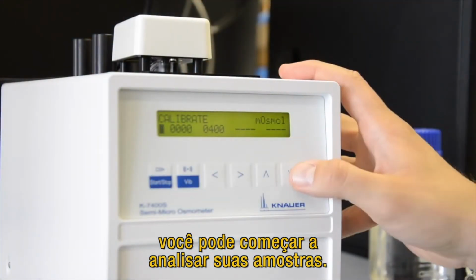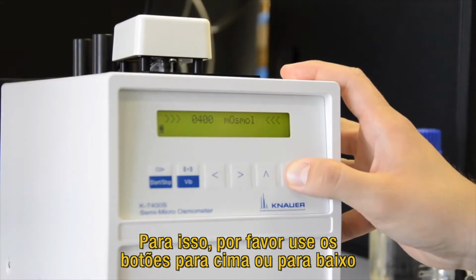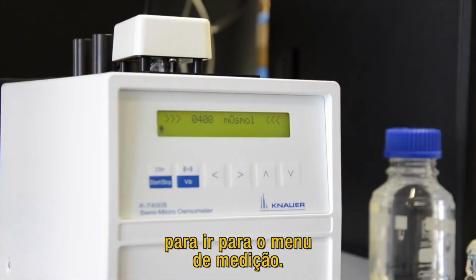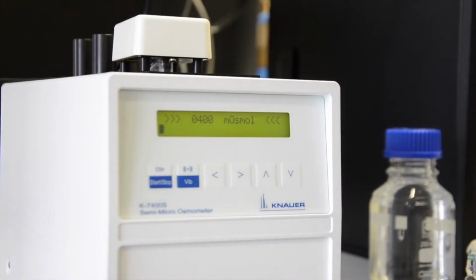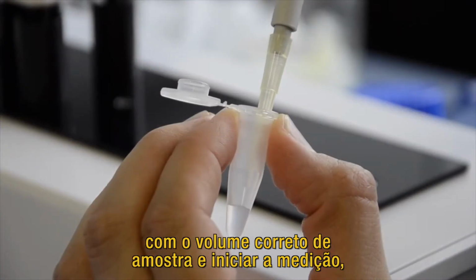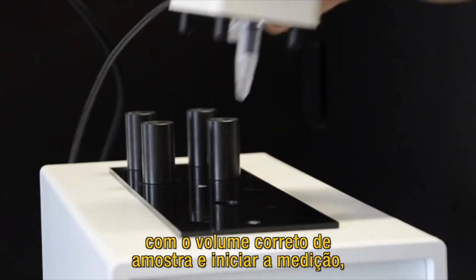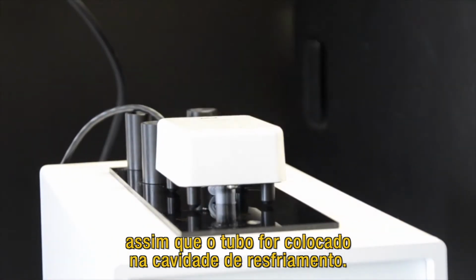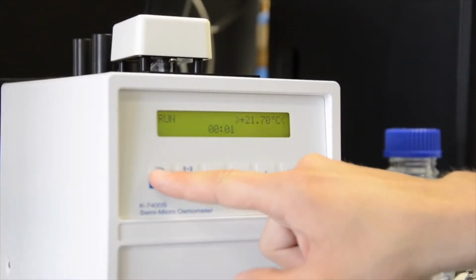After you calibrated the osmometer, you can start to analyze your samples. For this, please use the up or down button to go to the measurement menu. Now you can fill a new sample tube with the correct volume of sample and start the measurement after the tube is placed into the cooling cavity.